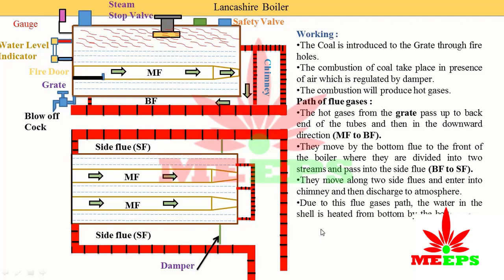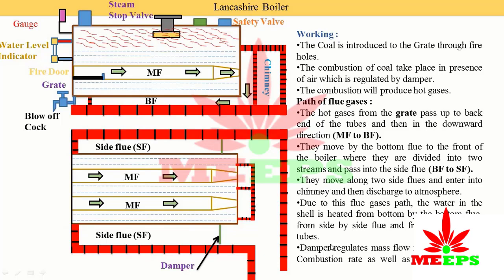The gases then move along the two side flues and enter the chimney, passing through the damper and from the chimney to the atmosphere. Due to this flue gas path, the water in the shell is heated from three sides: from the center by the fire tubes, from the bottom by the bottom flue, and from the two sides by the side flues. The damper regulates the mass flow rate of flue gases, combustion rate, and steam generation rate.